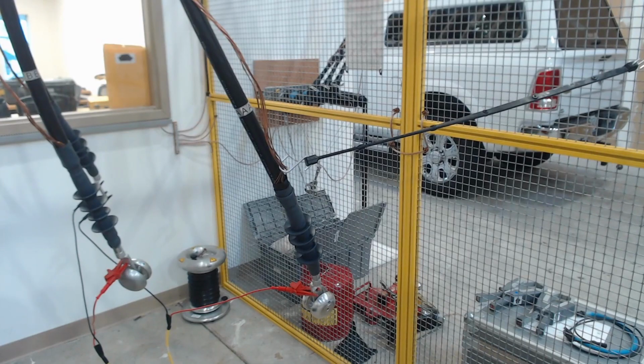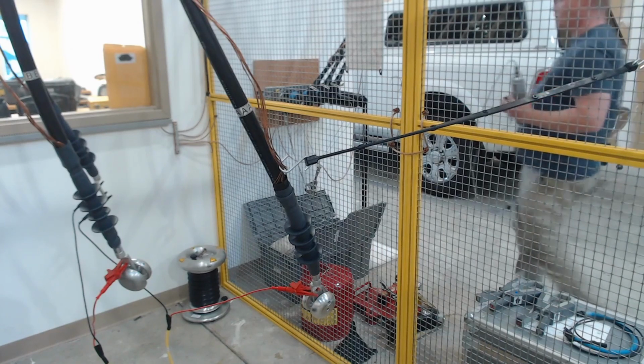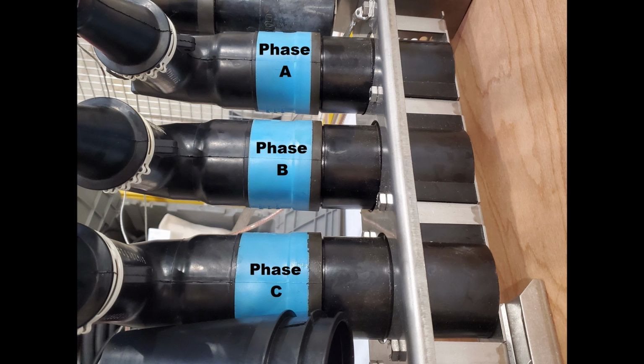All right, so what we have here is a 3-phase cable setup in direct mode. A little bit more representative of what you might find out in the field. So what we have here is A phase. We are connected through L1, and then our black return is turned to C phase. L2 is on our B phase, with the black lead return going to C phase. On the far end of our cables, we have all 3 plugged into a 3-way parking bushing here. So all 3 of them are connected. All the shields are grounded, but all 3 on the far end are connected into one bushing there.